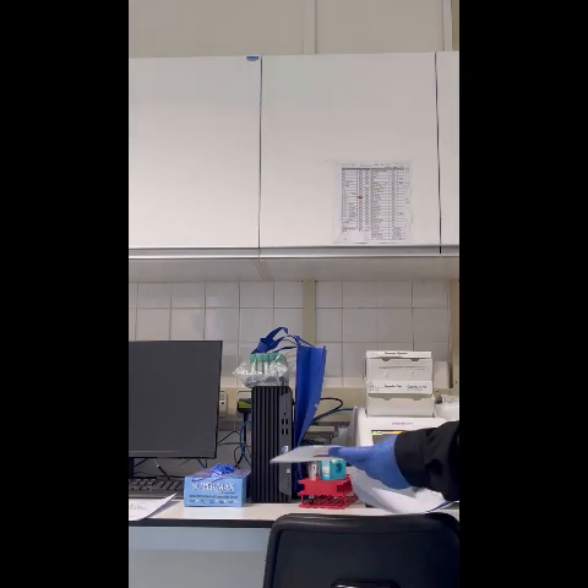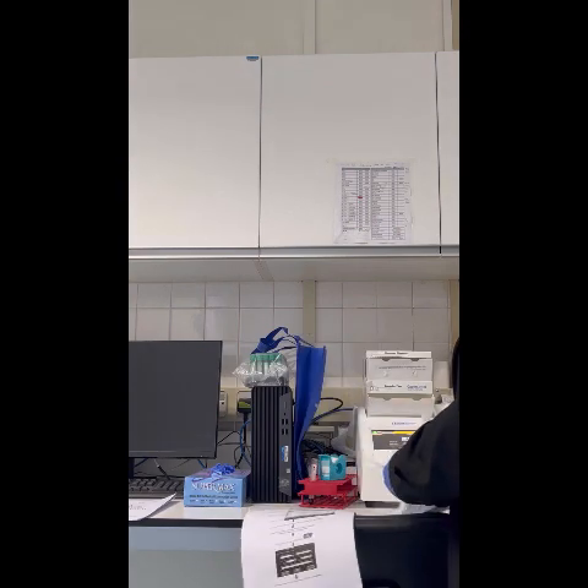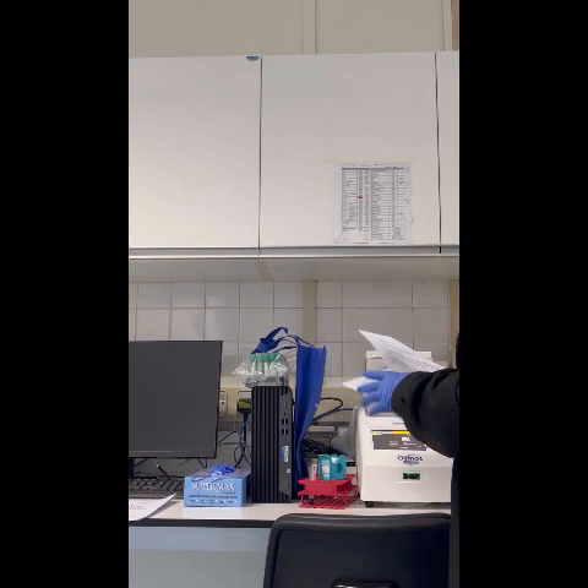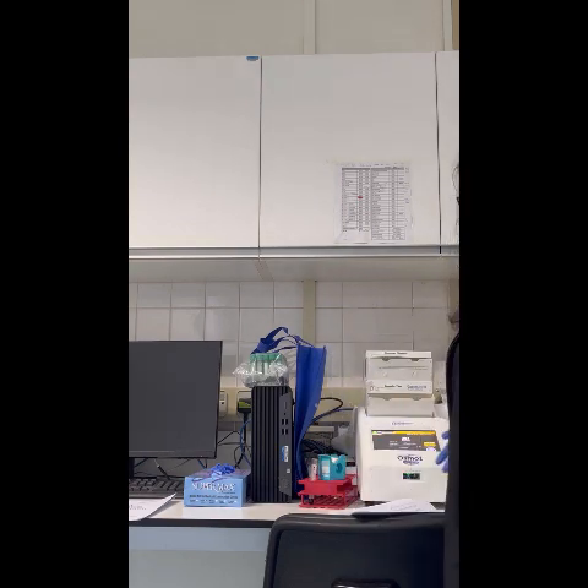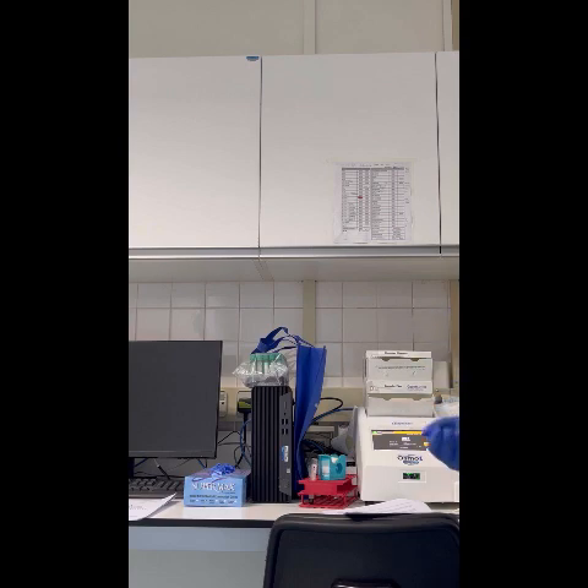For maintenance for this, there are 3 types of maintenance. One is cleaning the air vents, so there's a fan behind here for accumulation of dust, but we can do it monthly because we are in an air conditioned area, so we might not get a lot of dust in the air vents. Cleaning of instrument exterior, so the exterior is this part, so if there's any blood stains, you have to use an alcohol swab to wipe off, and this can be done weekly. And maintenance as needed, we have the chamber cleaning.